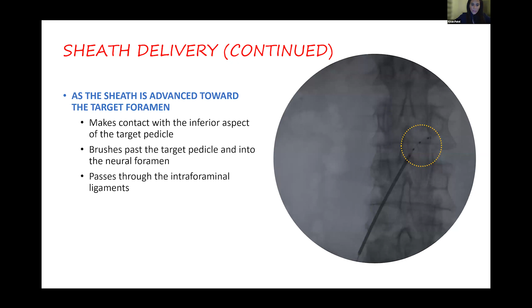And if you have a difficulty with the lead, then sub out the lead, meaning unlock the chain, unlock the lower lock, and then take out the lead, and then place your guide wire, and then try to tap with the guide wire because it's a bit more firm at its tip. But in general, I would say try to go with your lead. You know, give it a good go in terms of turning it, changing your angle, and then if you can't, then go with your guide wire.